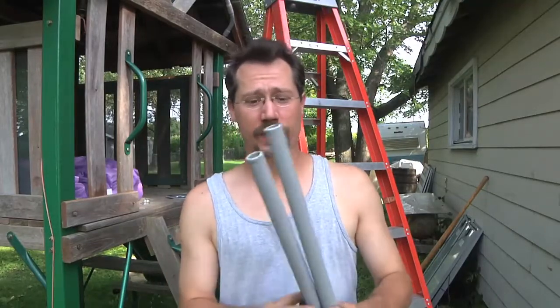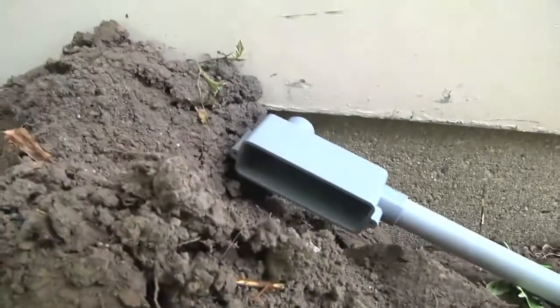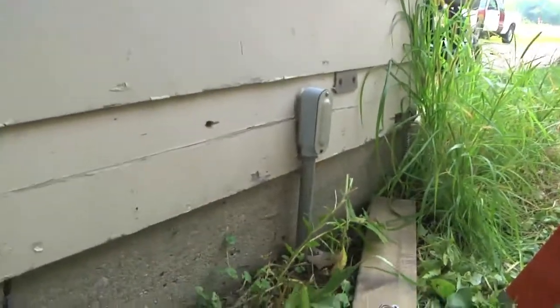Hi, I'm Ben, and I've been working on installing a solar panel on top of a kid's playset. Today I'm going to be taking all the PVC conduit, gluing it together and mounting it, and then fishing the wiring through. I already dug the trench and drilled a hole into the garage. I got this pulling box, which is a good way to get the power in there — I'm following what the commercial electrician did when this garage was originally wired up.